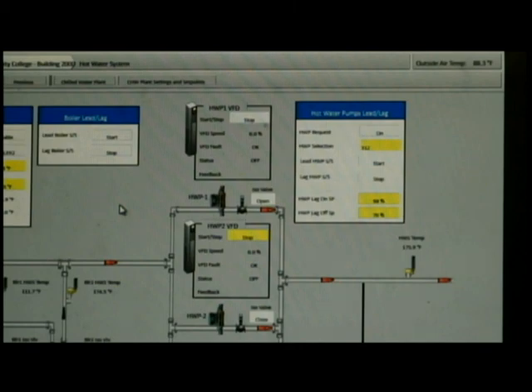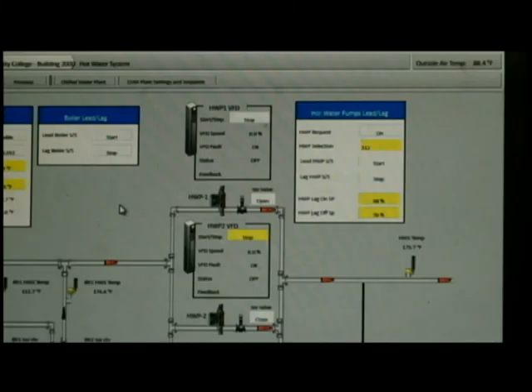Now, as demand decreases out there, that's where the lag off set point comes in of 70%. And it works just the opposite of the on. So if those two pumps, the lead and lag running, their common speed drops below 70% as it's set right now, then what you have is a lack of demand out in the loop such that you can go back to running just your lead pump. So once we drop below that 70% for a couple minutes to make sure it's a real case, then the lag pump shuts off, VFD turns off, gives it a few seconds, then the ISO valve closes off and we're back to just a single pump running. As far as the boilers go, we haven't had to run two boilers. One boiler has always been able to maintain the loop out there.